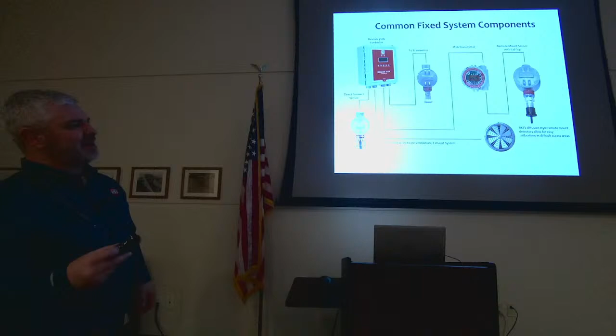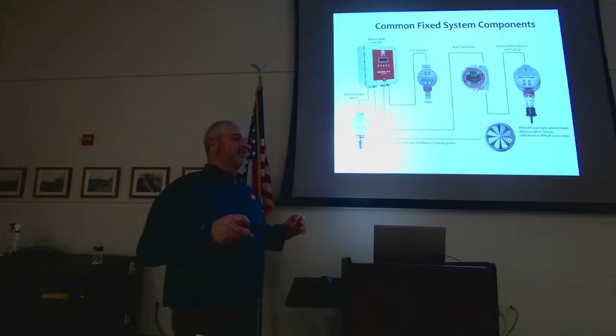And what that means is I can calibrate this whole system from here. With a direct connect, where there's no transmitter, I have to push buttons on here, then I have to walk over to the sensor and calibrate it, then walk back to the controller and accept the calibration. So if it's a short distance, I really like direct connect sensors. They're a little bit less expensive, and if it's not a pain to work on, it's a great way to go. But if you're 2,500 feet away, you don't want to be running back and forth.